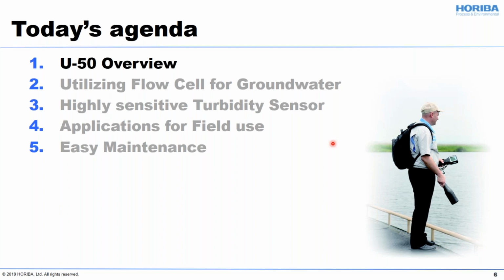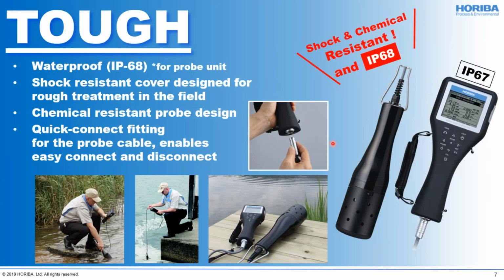I will start to talk about the U-50 meters. HORIBA's high accuracy, robust, and easy-to-use multi-parameter water quality checker. The first advantage of the U-50 is that it is tough in the field. The pictures on the right show the meter and probe. It is handheld size, so you can bring it to the field and easily operate measurements there. It also has a robust design optimized for field use. The meter has an IP67 waterproof class and the probe unit has IP68 class. Even if you drop it in water, it's okay, no worry.